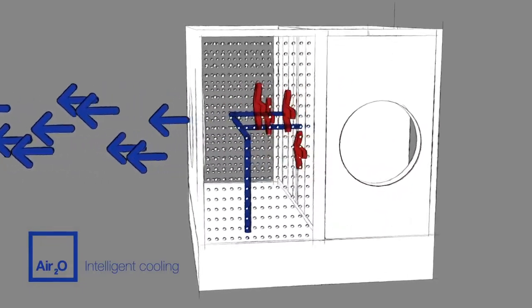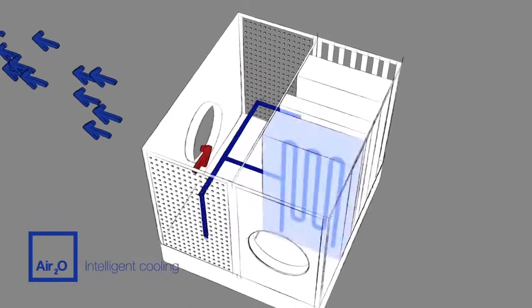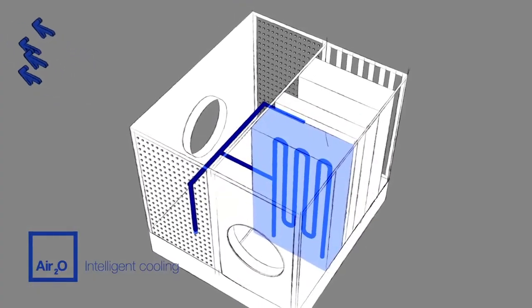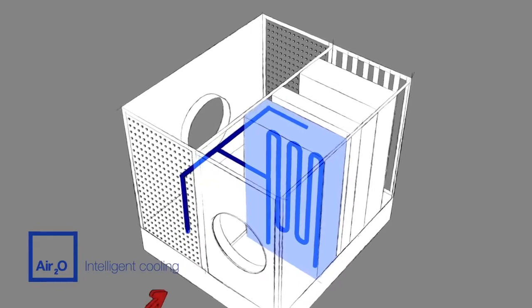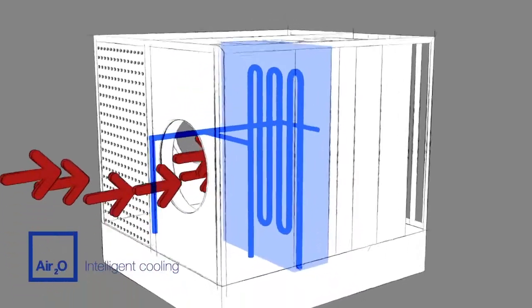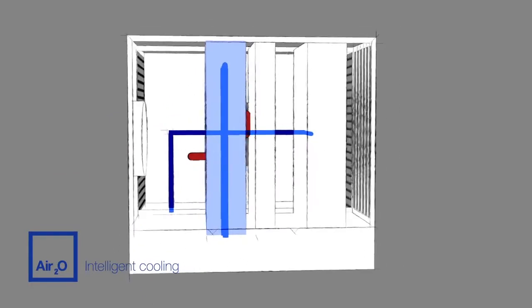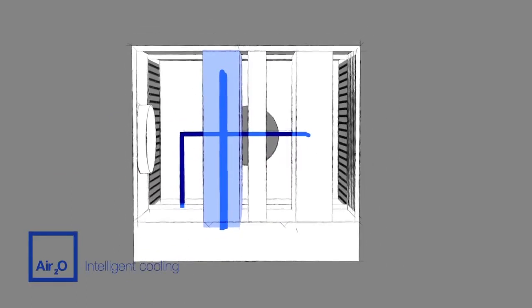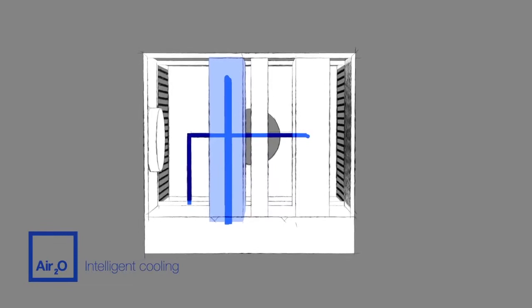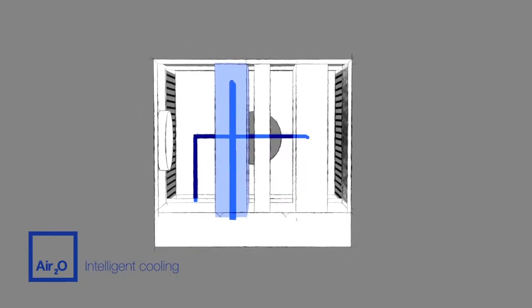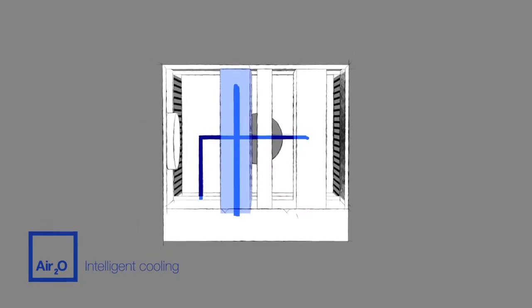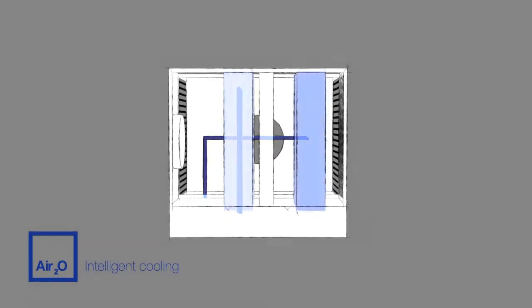As the warm air is cooled, so is the water. This cool water is then transferred to a high-efficiency heat exchanger, over which the primary outdoor air is passed to deliver the first stage of cooling with no additional moisture, indirect evaporative cooling. This same concept can also be utilized to provide ultra-efficient heat recovery of air-conditioned buildings.